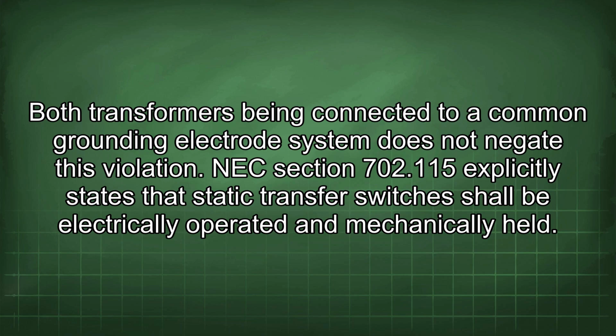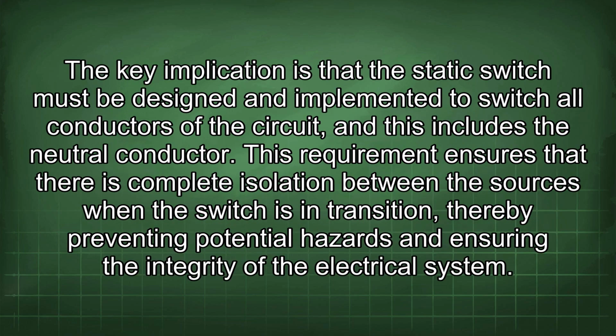NEC Section 702.115 explicitly states that static transfer switches shall be electrically operated and mechanically held. The key implication is that the static switch must be designed and implemented to switch all conductors of the circuit, and this includes the neutral conductor. This requirement ensures that there's complete isolation between the sources when the switch is in transition, thereby preventing potential hazards and ensuring the integrity of the electrical system.